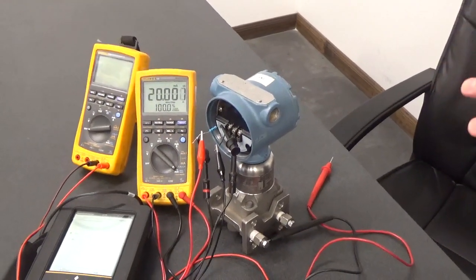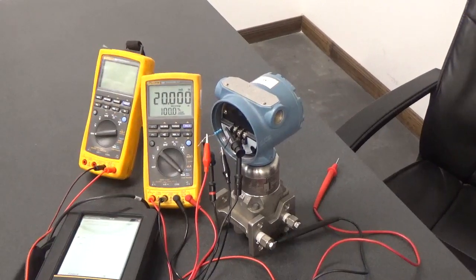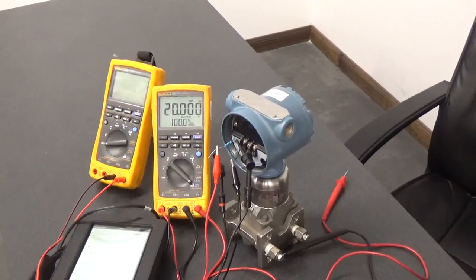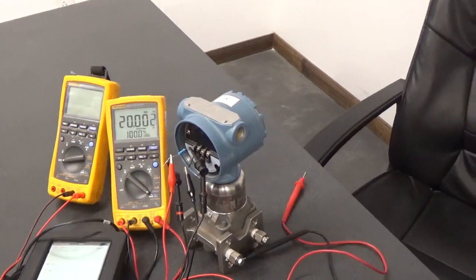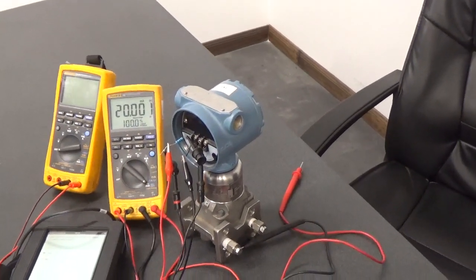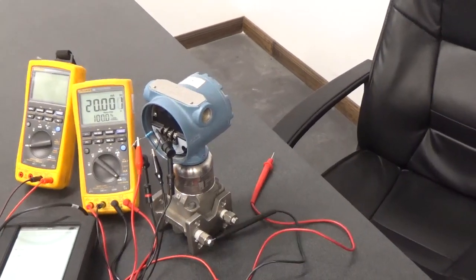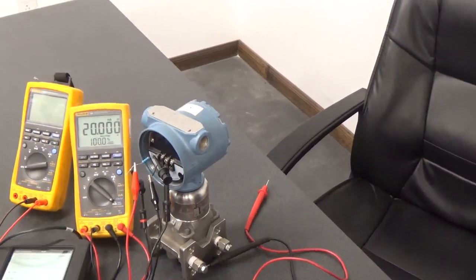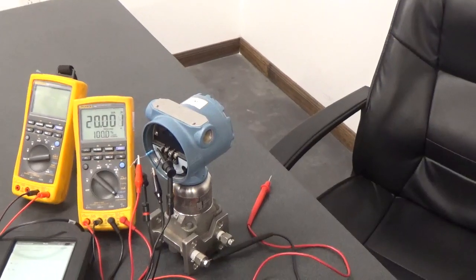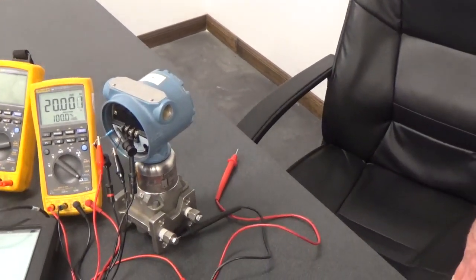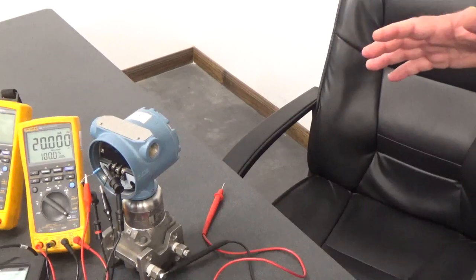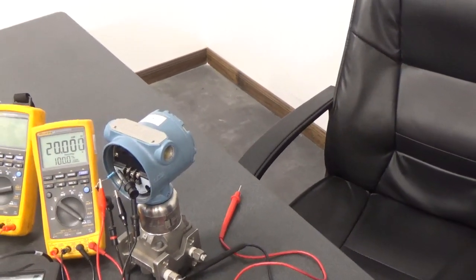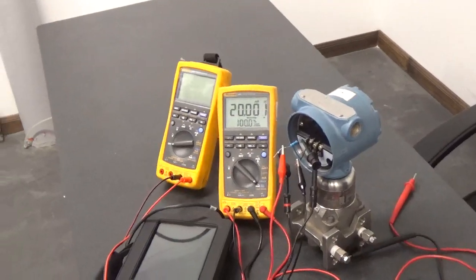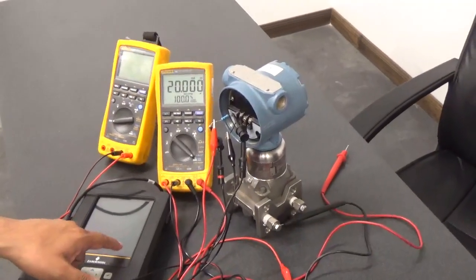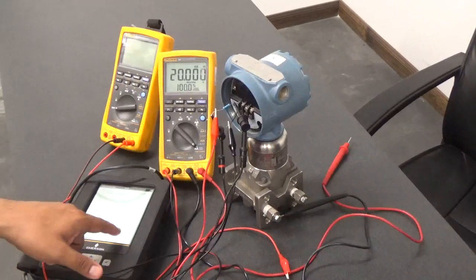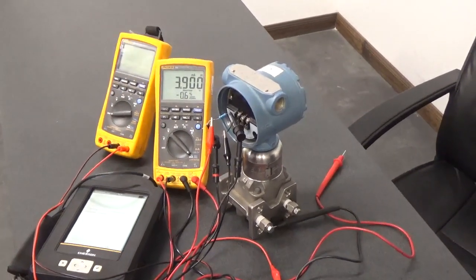Now, when you install these instruments, is there a standard? Say that 3.980 would be. Every company's going to have their error spec. Some companies 1%, some companies 2%, some companies it's a decimal point. They say, okay, between 19.9 and 20.1 is good. Does the process sometimes dictate that too? No, the engineering dictates that. You do what the engineers tell you. Gotcha. If you want to make a choice, then you become the engineer. Then you'll make that. But that's a company thing. Understood. We good? Mm-hmm. Okay, very good.